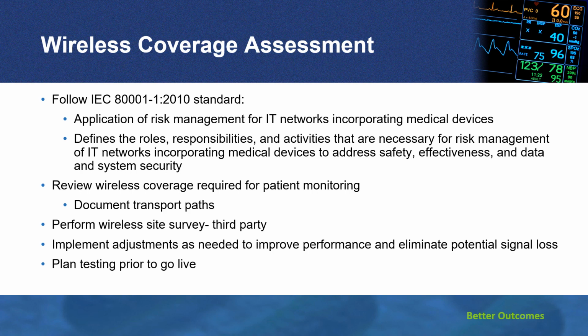So, wireless coverage assessment. Some of you who are not technical may not be familiar with this, but there's an international guideline that talks about standards for wireless and wired healthcare networks. I found that this is really invaluable for hospitals for guidance, because they need to understand what the risks are. So this is a way to apply risk management to IT networks that incorporate medical devices. They also need to identify roles, responsibilities, and activities that are necessary for risk management of the IT network, incorporating medical devices, to address safety, effectiveness, and data and security.